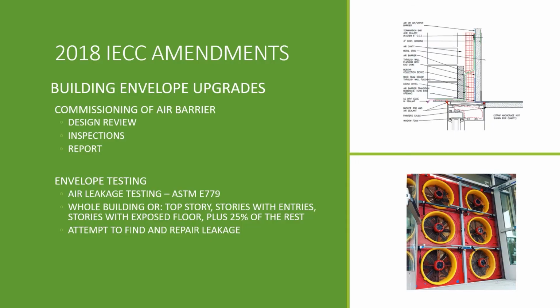So what are you going to do with a very large building? It has been addressed that you would do the top floor, any floor with entries to it, any floor that has an exposed floor, like above a parking garage or something, or an overhang, and then 25% of the additional square footage of the envelope on all the other floors has to be tested. But that's what it is. It's really putting a fan on each floor of a building and measuring the airflow. Yes, no, do we meet it?